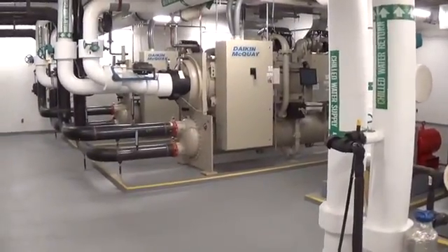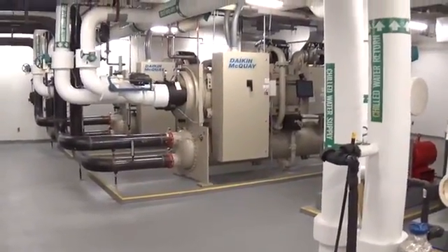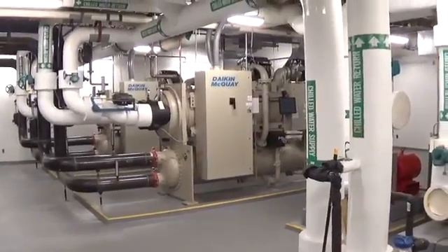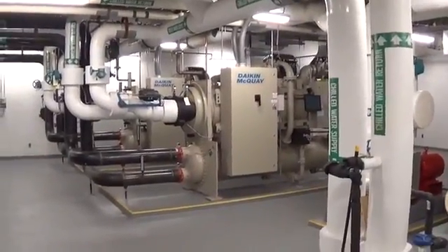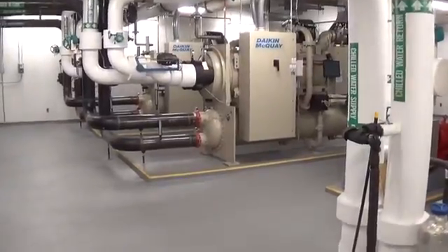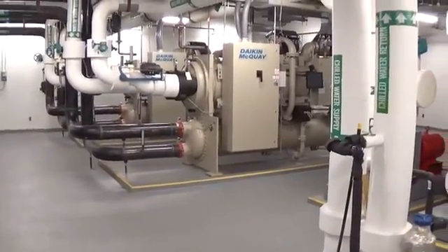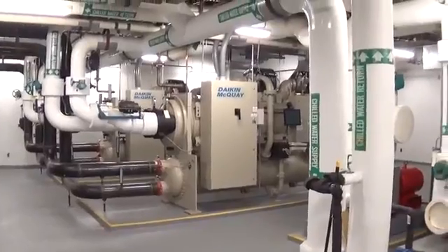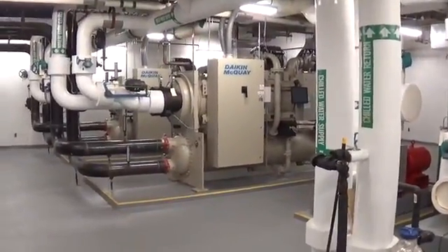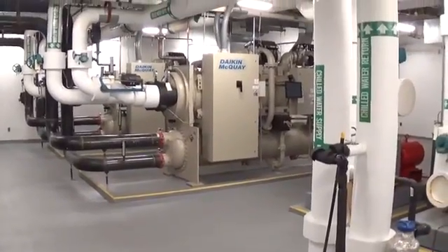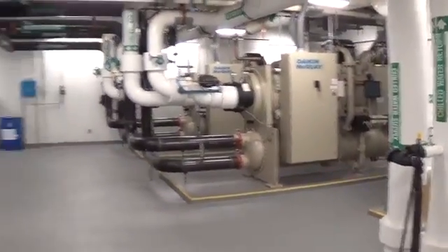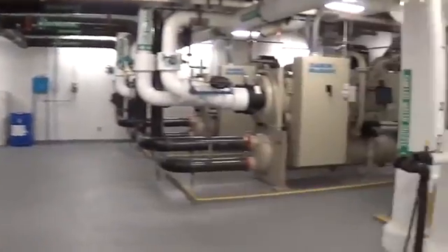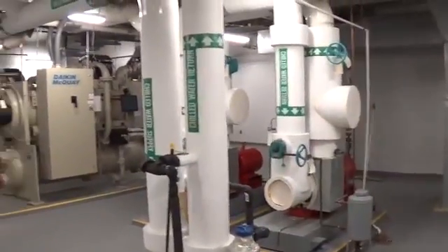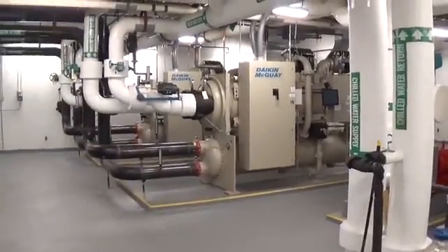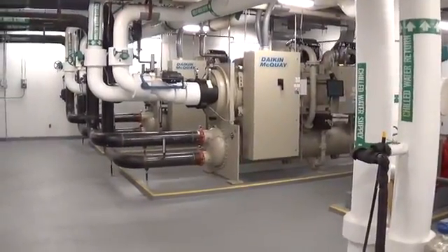This is just basic information on how a chiller plant operates. This, of course, is the cooling systems for the building. And this is an office building, so this is comfort cooling. We have a small data center operation here, but it's handled by independent little package units. Not a large data center operation. Sorry for all the noise here, but chiller plants tend to be quite noisy. So we'll run you through real quick here, basic chiller plant operation.